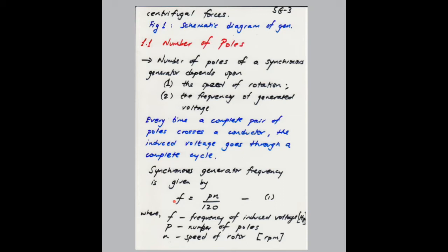So you will see that in the machines that we will look at in our tutorials or examples, there are two types of machines. In terms of frequency, you'll find that some machines are rated at 60 hertz. So these machines are more designed for the American power utility because they use 60 hertz. And the machines that are designed for South Africa or the African continent and Europe basically work on 50 hertz. And obviously then they will have a different number of poles and speed to generate 50 hertz as compared to the 60 hertz machine.